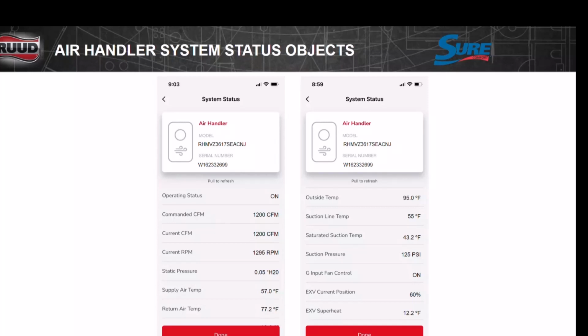That goes back to what you were talking about earlier, that undersized duct system. These units are smart enough now to tell you that you have an undersized duct system. Your homeowner is always going to tell you, well, the other one worked just fine. If you have an EEV, it's going to tell you what position the EEV is in.